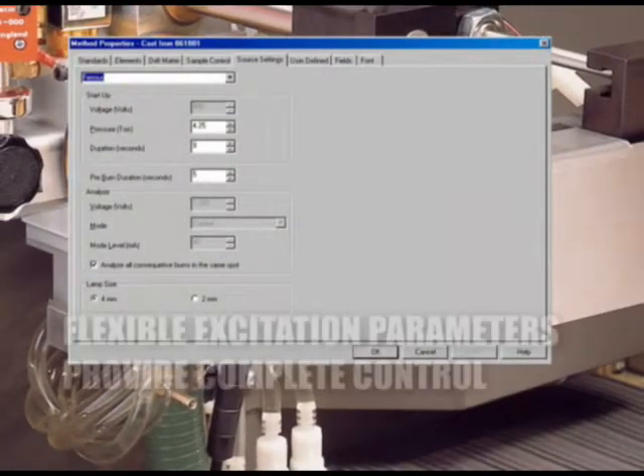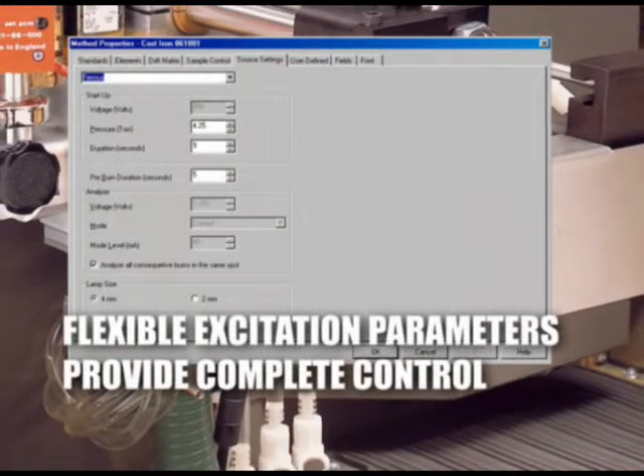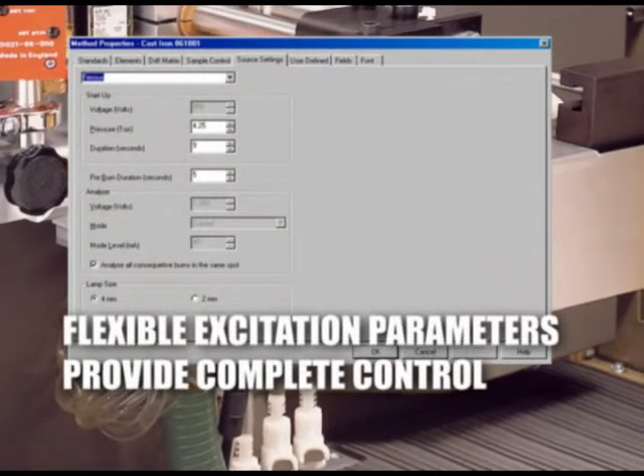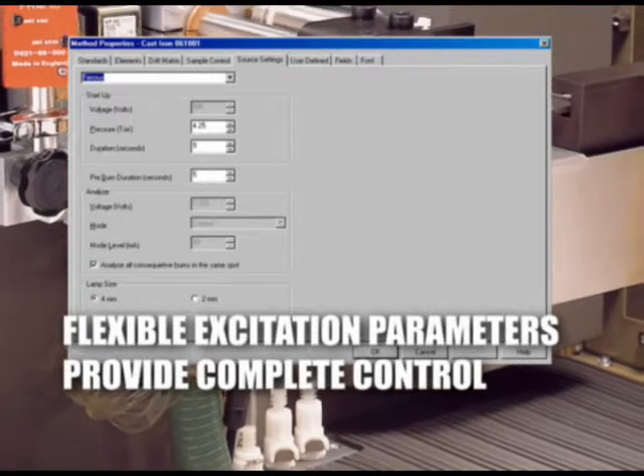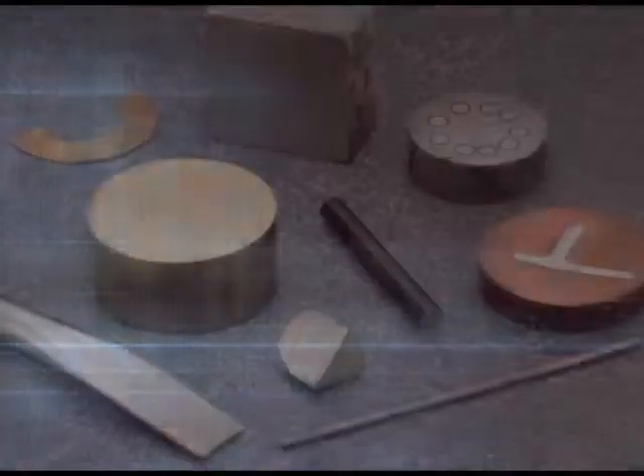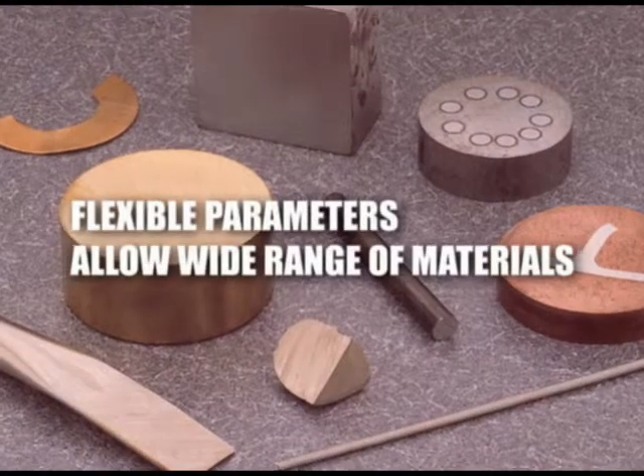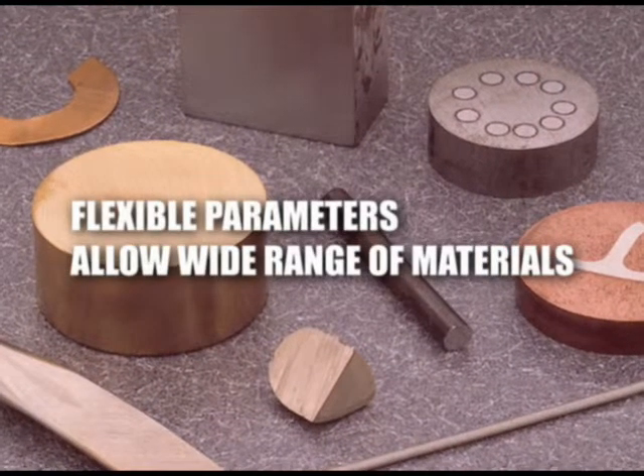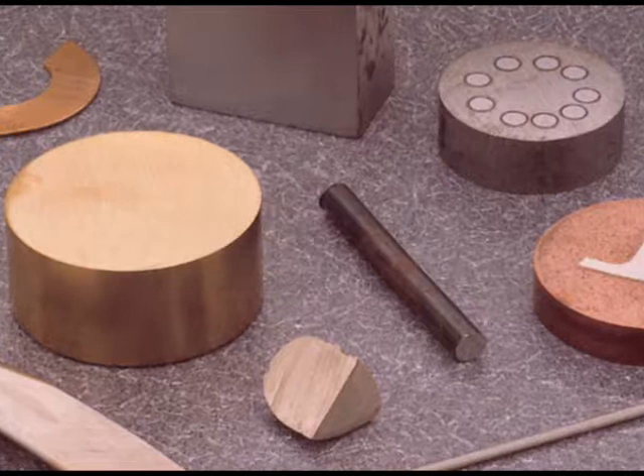Analysis characteristics for lamp evacuation time, stabilization time, and lamp pressure assure proper sealing of the sample to the lamp and proper stability of the lamp environment before the analysis begins. The flexibility of each set of parameters allows a wide variety of samples to be analyzed with optimum precision and minimal interferences.